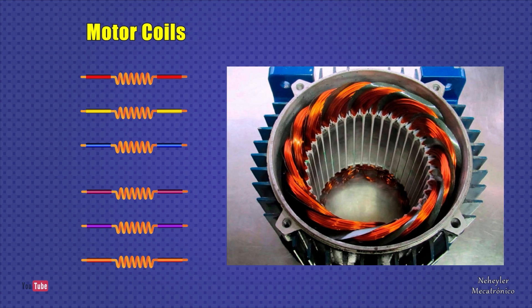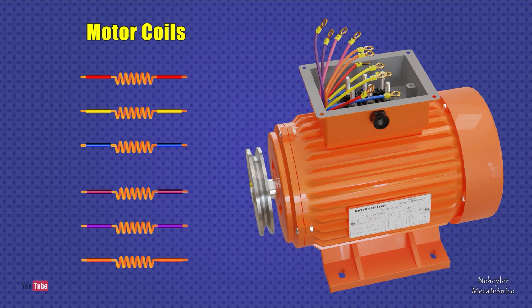The coils of an electric motor are the copper windings that are in the stator. If over time or due to misuse of the motor, the copper cable that makes up the coils deteriorates or breaks, then to repair it, it is necessary to rewind it — that is, make a change in the cable winding inside the engine. Before explaining how to make delta or star connections, it is necessary to know how the terminals of each motor coil are named or labeled.